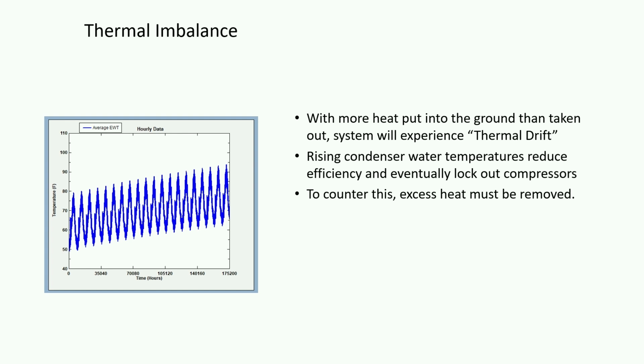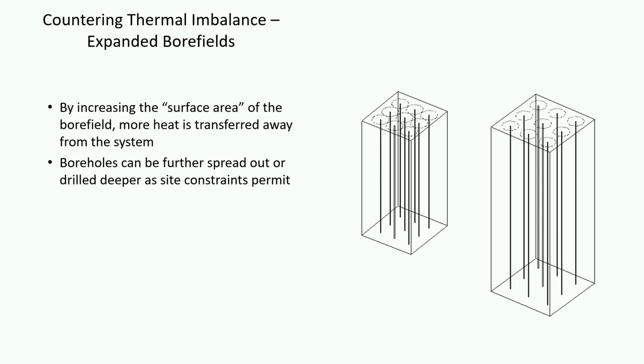This is going to reduce your cooling efficiency. It'll help your heating efficiency a bit, but it will reduce your cooling efficiency. And if you allow this to run on over 50 years of operation of a building, eventually you're going to lock out your compressors. Your system is not going to work at all. So to counter this effect, we have to find some way to get rid of this excess heat year over year. We'll go through a couple options. We have some levers we can pull to take care of that.